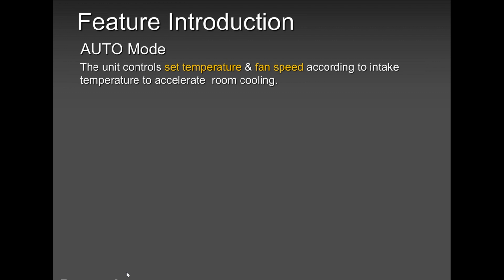But again, as far as I'm concerned, with all my experience with this heat pump technology, I am not a big fan of auto mode, because auto mode will run in cooling or heating, and then once the room is hot and it goes above 5 degrees, it switches over. So all that heat that you pumped into that room is going to be taken away by dumping in cold air. So that's not a good idea. It's not a good savings idea as far as I'm concerned.